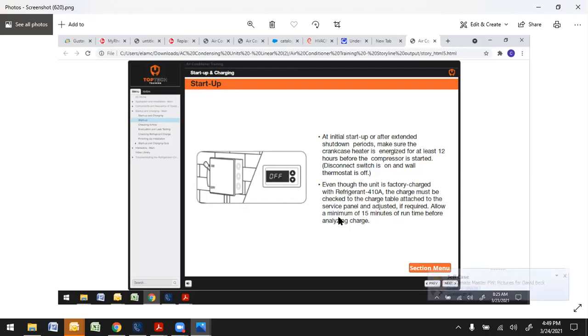Now this is a big one here. Allow for a minimum of 15 minutes of runtime before analyzing the charge. At least let it run 15 minutes. It takes a good 15 minutes before it really starts to stabilize. If you have two-stage units or inverter units, you really need to let those run 30 to 40 minutes before you start making adjustments. If you make adjustments too quickly and then bail out before it stabilizes, it's easy to overcharge it.